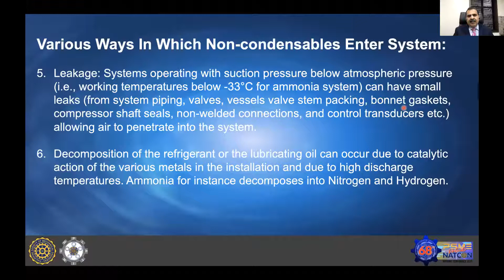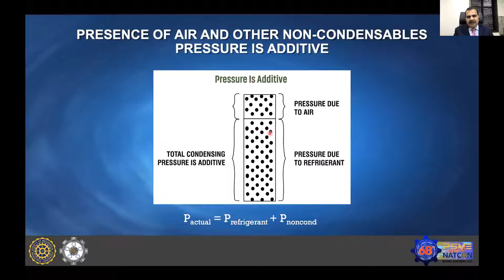When the pressure of the air or other gases enters the system, it adds to the total pressure. So our actual pressure becomes the refrigerant pressure, which theoretically, as per our refrigerant chart, should be the actual pressure for condensation, plus the non-condensable gases. This total pressure becomes one pressure. So this pressure is additive. The more air pressure there is, the more the condenser discharge pressure will increase. We have a higher pressure on the discharge side of the system.